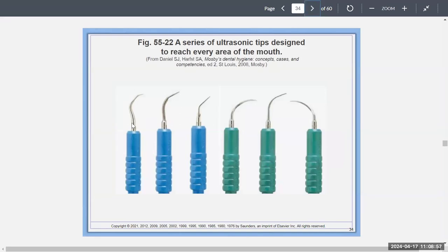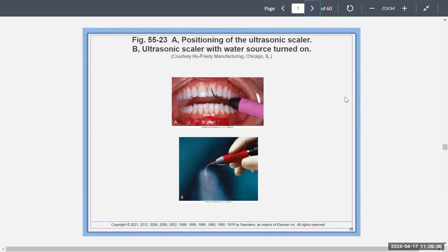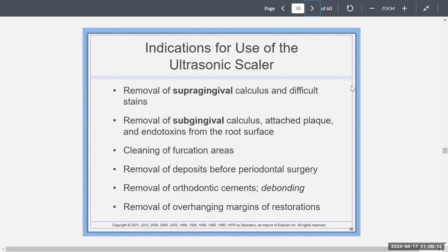The ultrasonic tips vary for the Cavitron — some are angulated, some are round — depending on what area of the mouth or what case you're dealing with. Indications include removing supragingival calculus or difficult stain, removing subgingival calculus, attached plaque, or endotoxins on the root surface, cleaning furcations, removing deposits before surgery, removing orthodontic cements and bonding, and getting rid of overhanging margins of restorations.